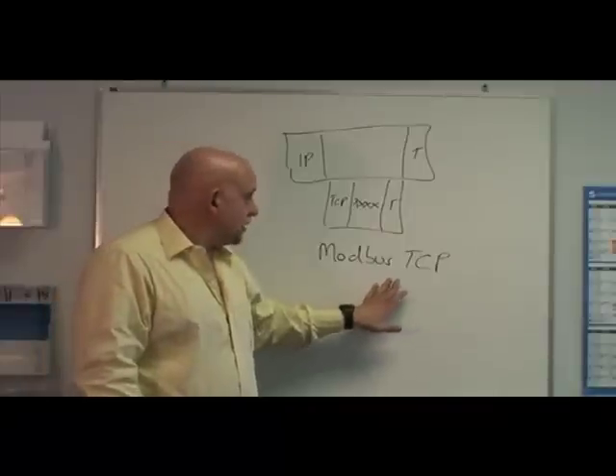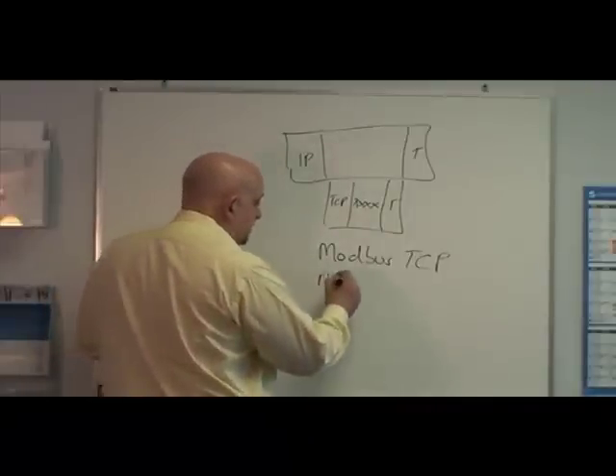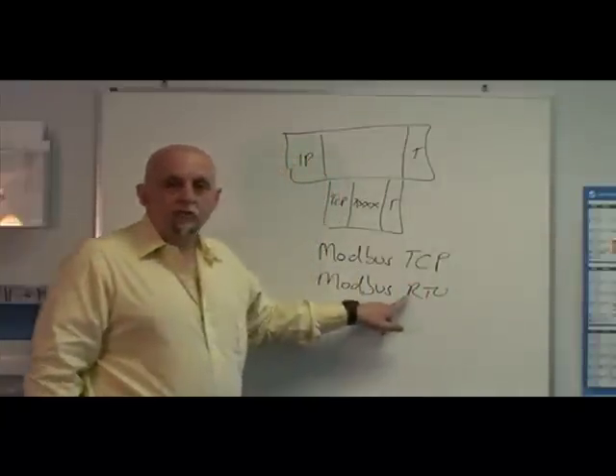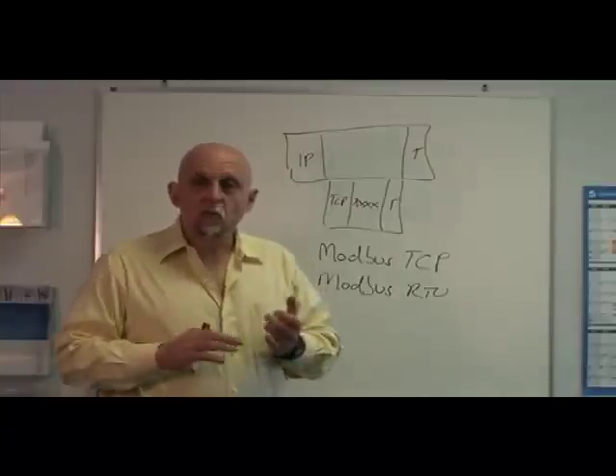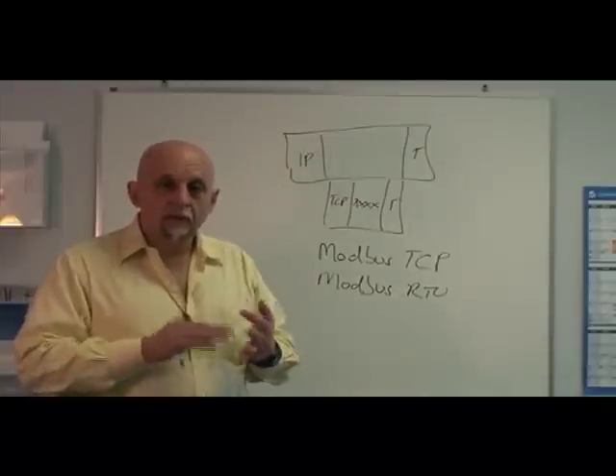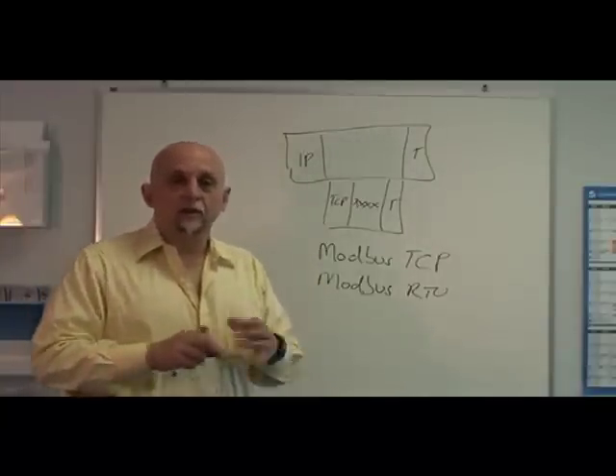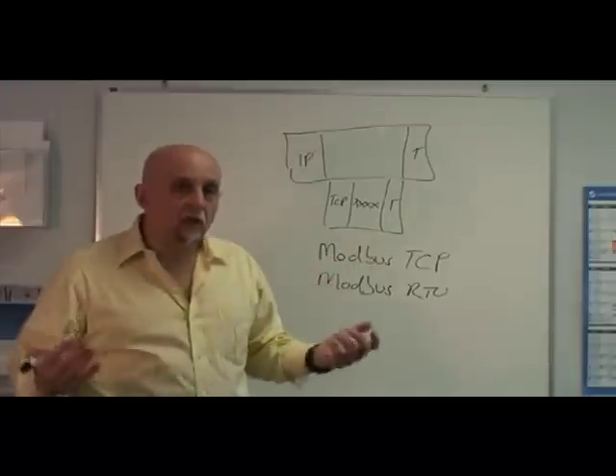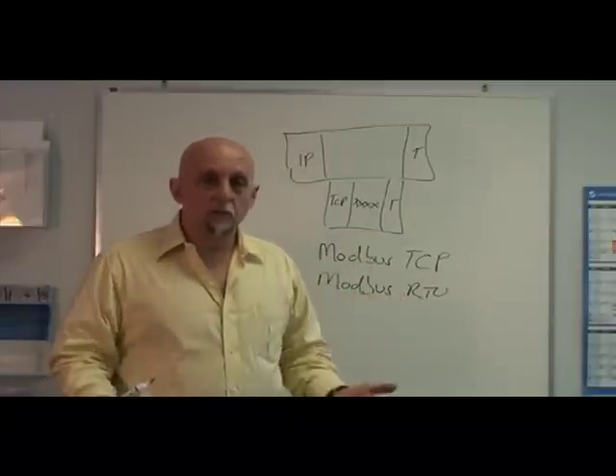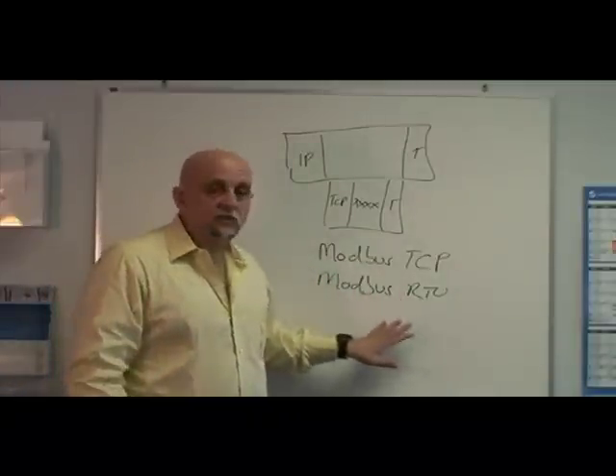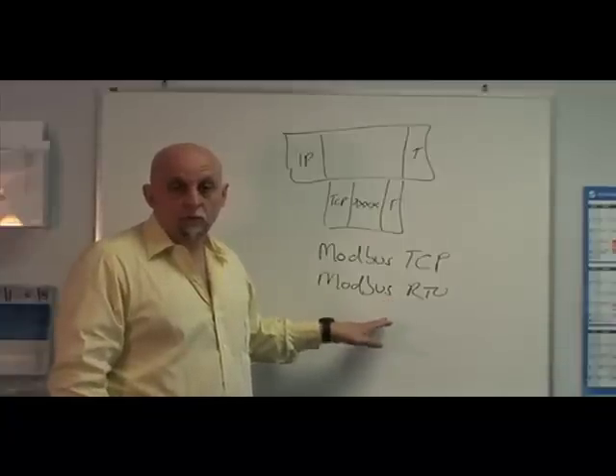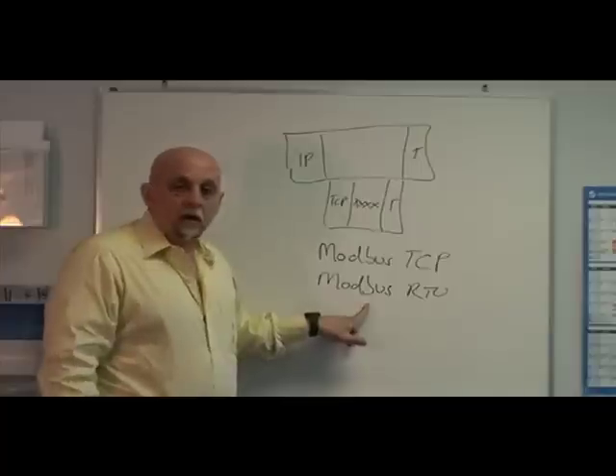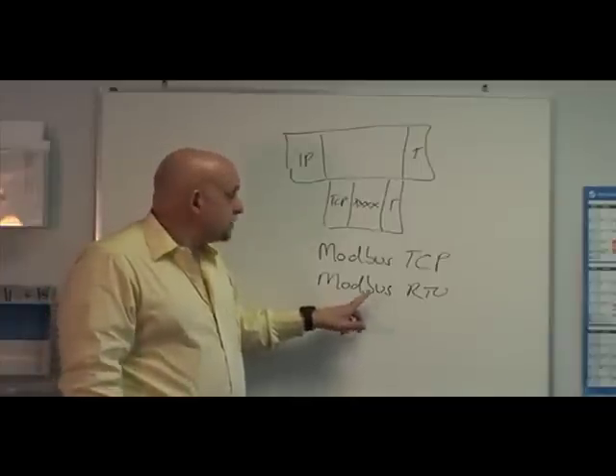Now in the Modbus world, not just Modbus TCP, but Modbus RTU, which is the 485 version of Modbus, data is represented as registers and coils. Registers are simply 16-bit unsigned data values. Coils are single bits. So every device on a network has some number of registers, has some number of bits. You can actually have 64K worth of registers and 64K worth of bits. Most devices don't have that many.